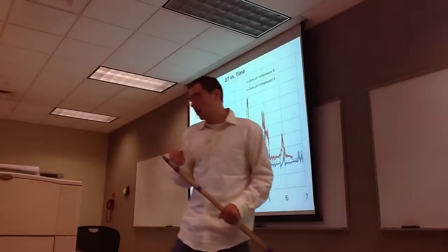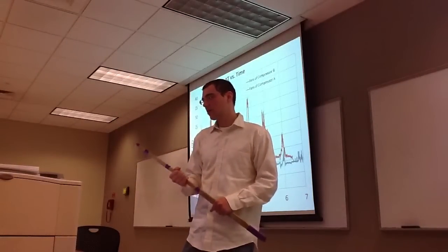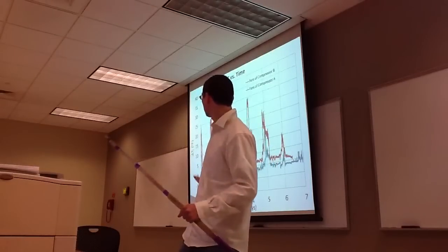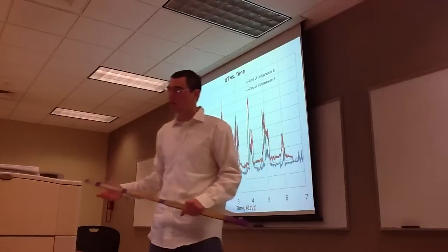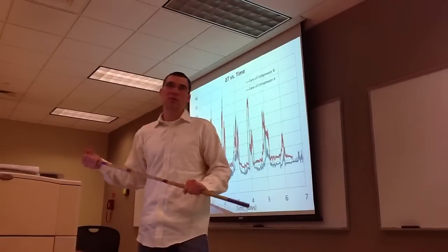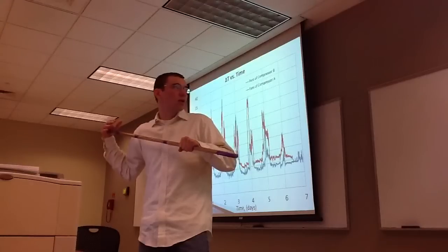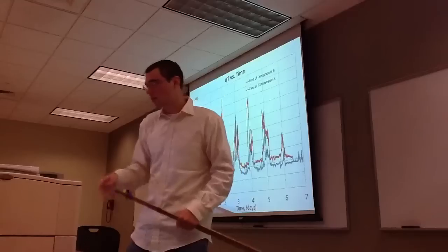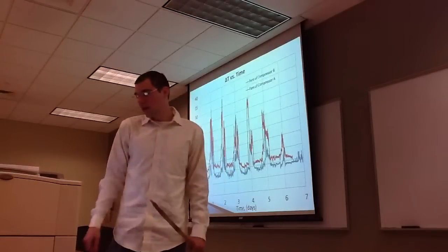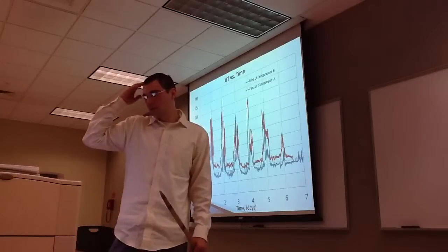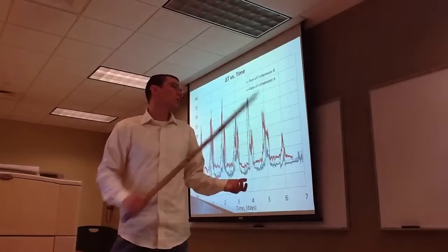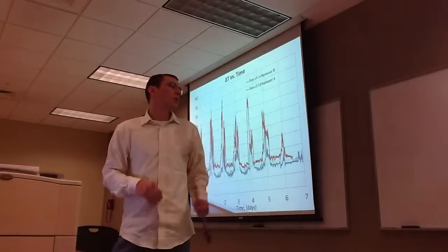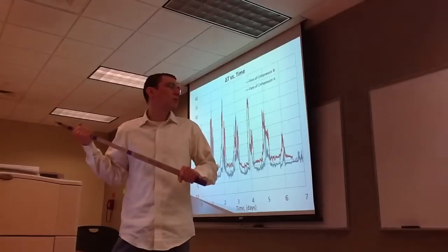So this is the data taken over a week's time of the changes of temperature between the top and the bottom of the cooling tower. So basically how much temperature was transferred, or how much the delta T was for an entire week. And side B is always lower for some reason. Not always, but it looks about that way, pretty much all the time, even though it is running the most.